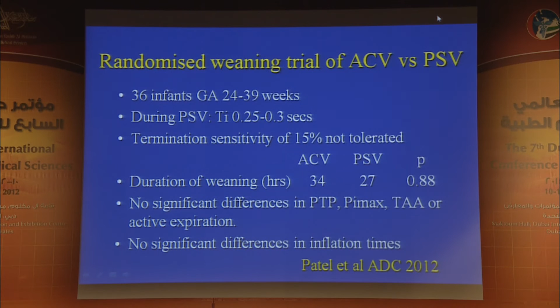To our surprise, the termination sensitivity maximum of 15% was not tolerated. And in some ventilators, they only allow a termination sensitivity of 15%. And indeed, in the majority of infants, we were only able to use a termination sensitivity of 5% if we didn't want the inflation time to be lower than 0.25 of a second. We found in our randomized groups the duration of weaning was not significantly different, and indeed we found no significant differences in our physiological outcomes: the work of breathing, the respiratory muscle strength, and the degree of asynchrony. The reason for that was there were no significant differences when we looked at the airway pressure waveforms and inflation times. So essentially, with assist control and pressure support with attention to the inflation time, we are delivering the same modality, and both are efficacious weaning modes.